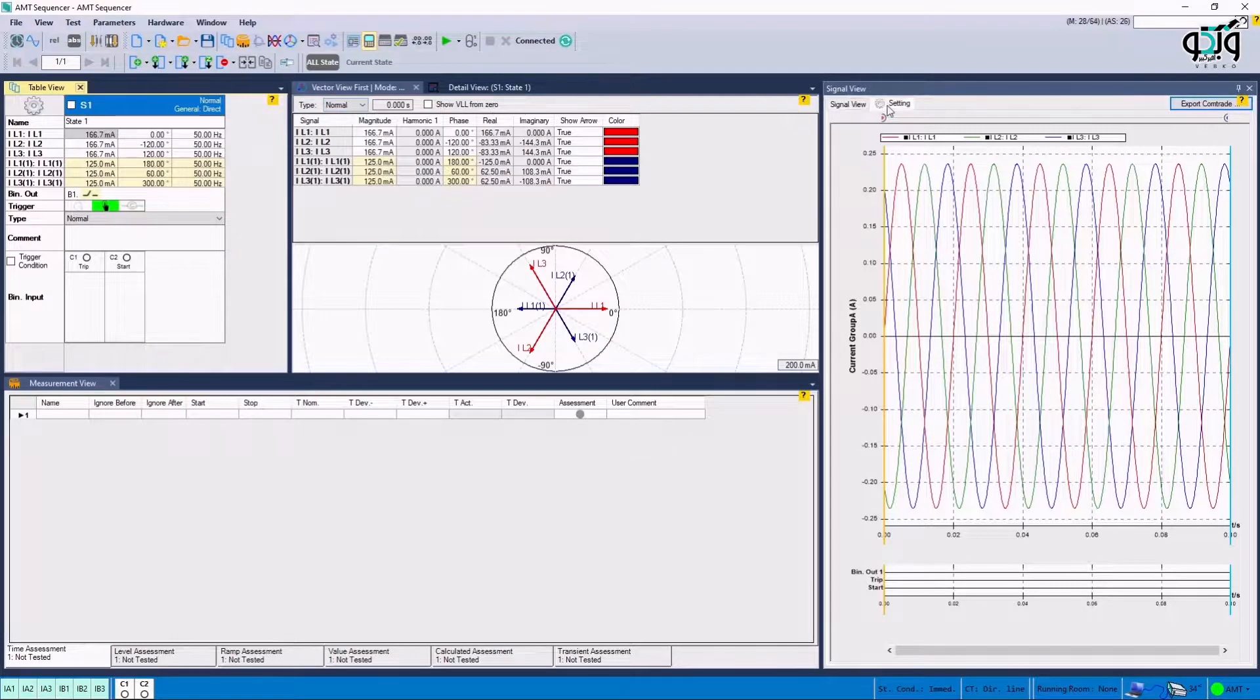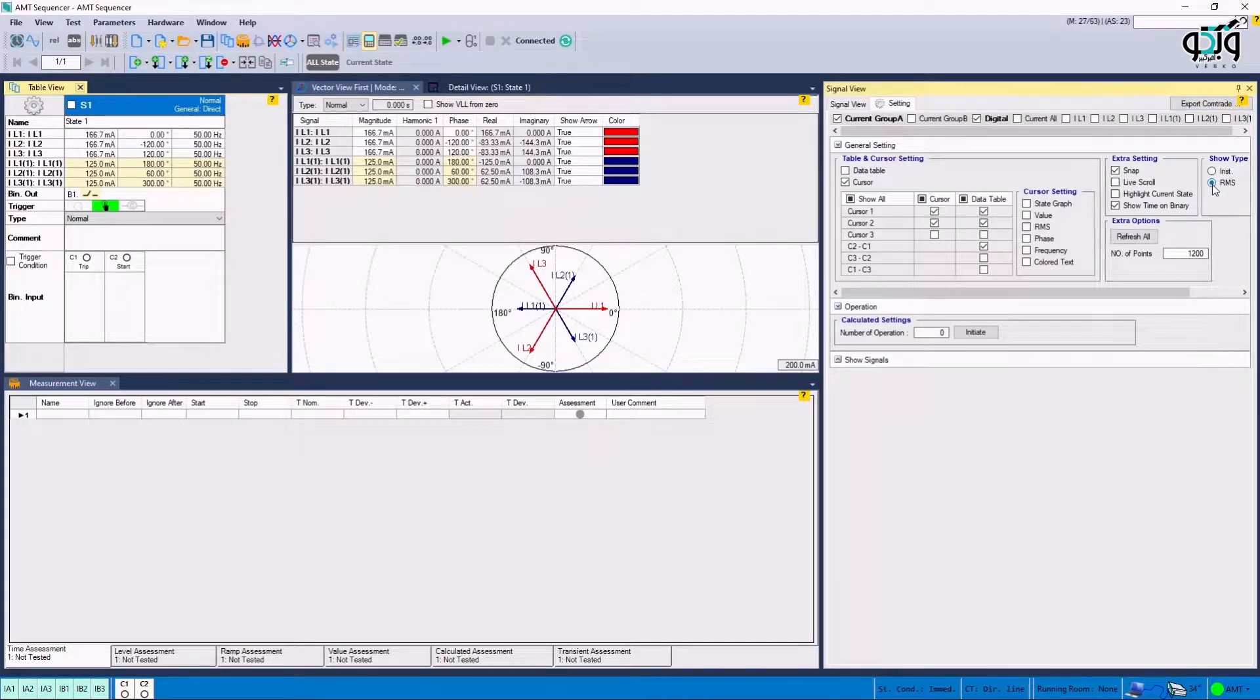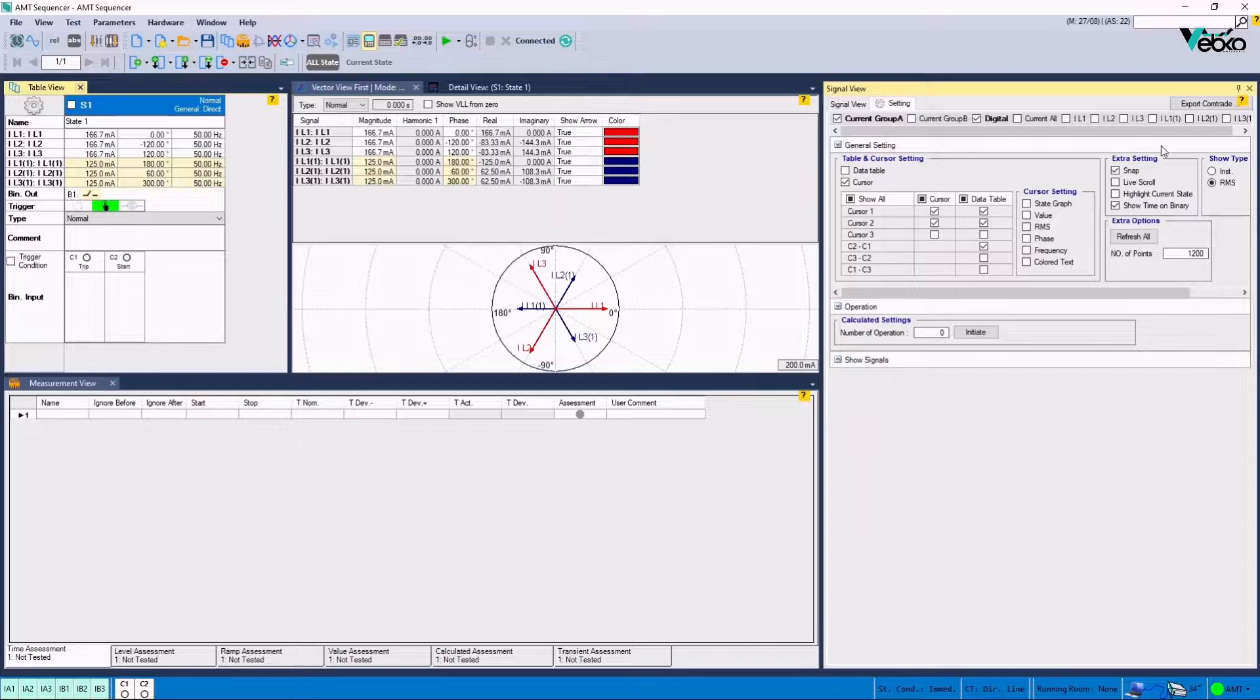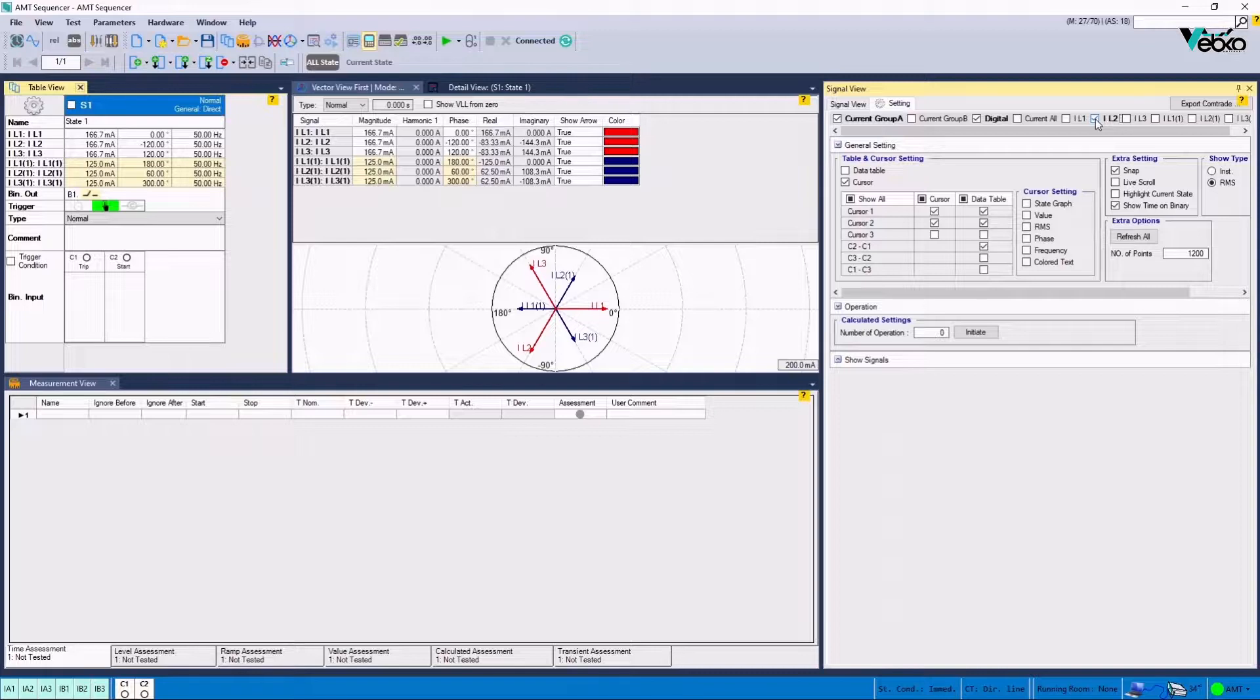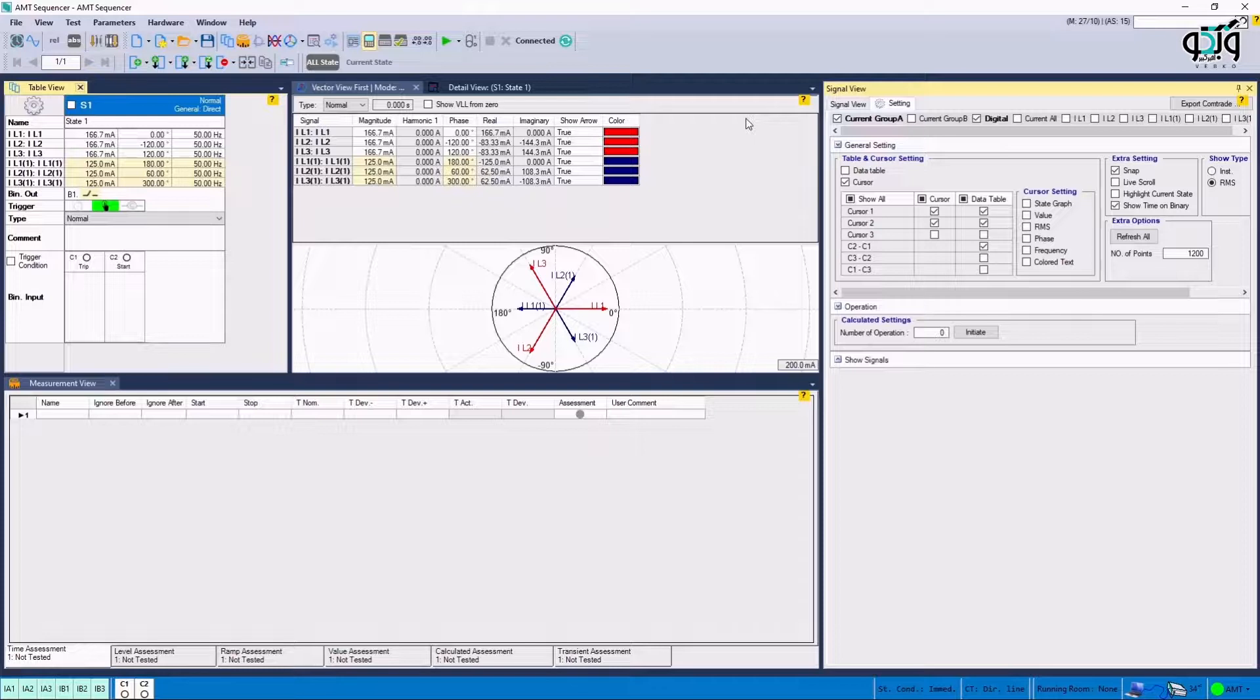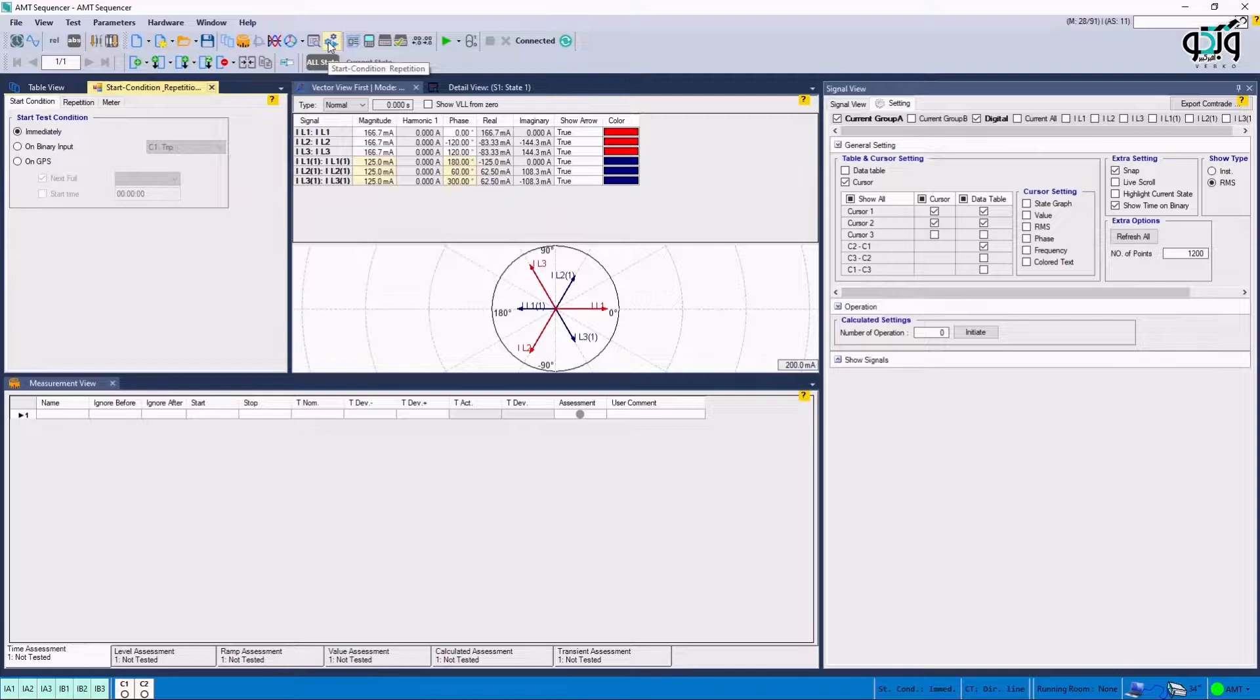By default, the currents are considered momentary, but it is possible to select average values by selecting Setting Header and then RMS option. If this stability test is only applied for one phase, it is possible to mark the checkbox for the corresponding phase, so that only the signals related to the phase are displayed. In the next step, the test's start conditions are adjusted. In this section, by selecting the Start Condition Repetition option, a new page opens.